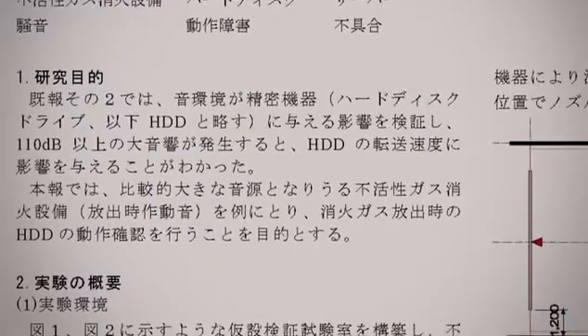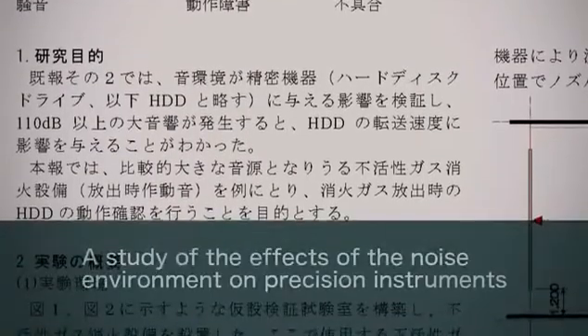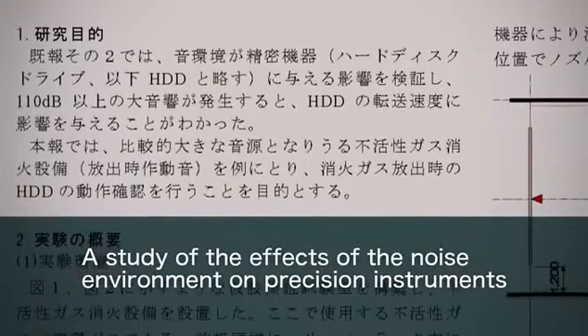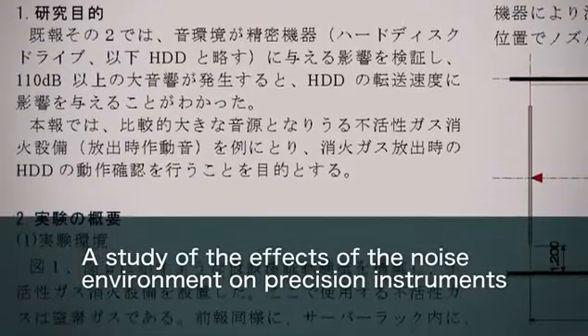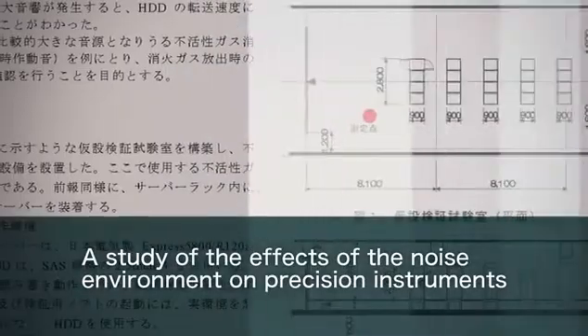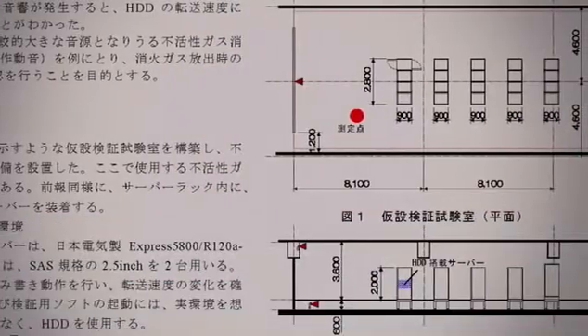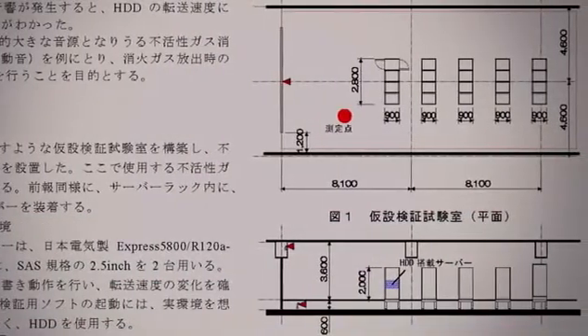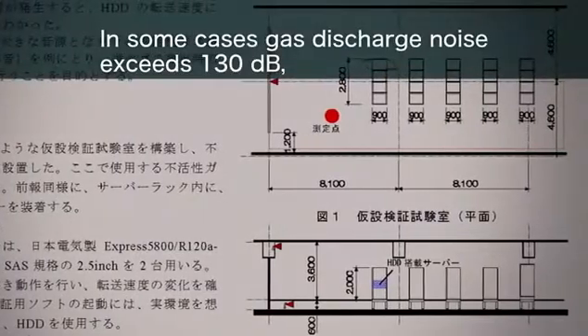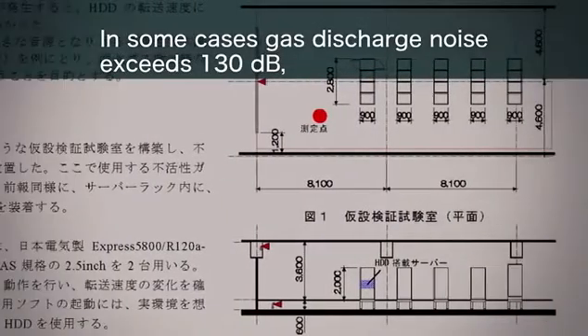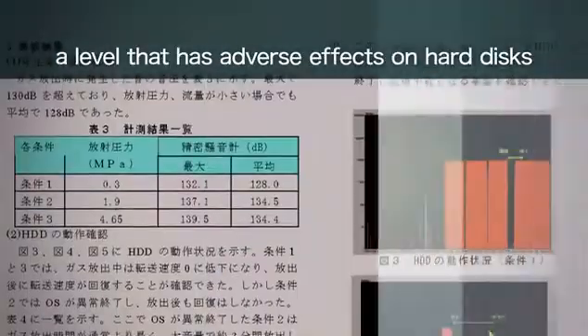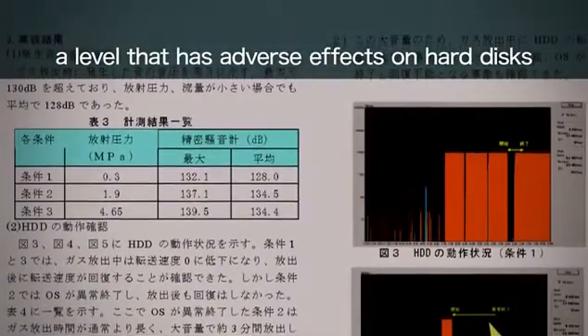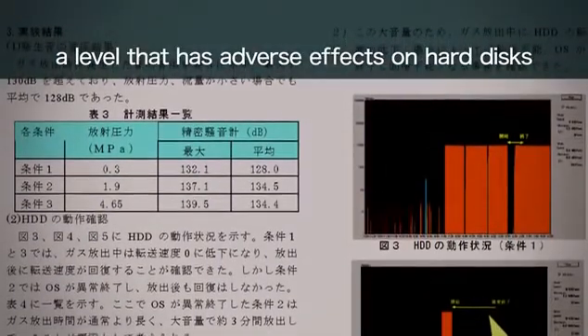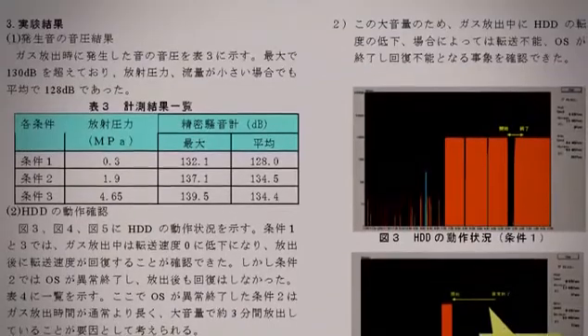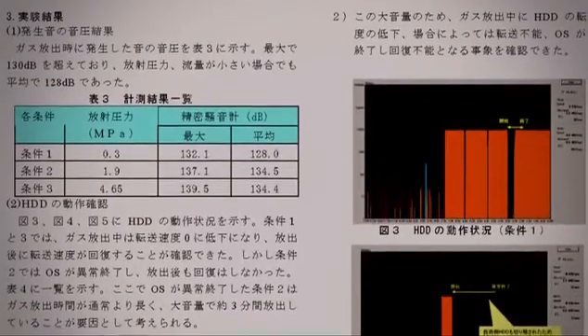This paper, entitled A Study of the Effects of the Noise Environment on Precision Instruments, was presented at a meeting of the Architectural Institute of Japan. It suggests that sound pressure exceeding 110 decibels has an effect on hard disk transfer speed, and that the gas discharge noise of inert gas fire suppression systems, which sometimes exceeds 130 decibels, can produce such effects.